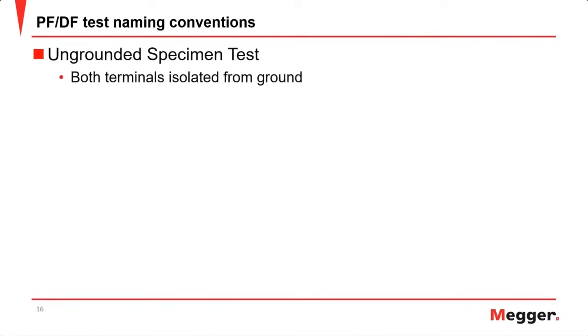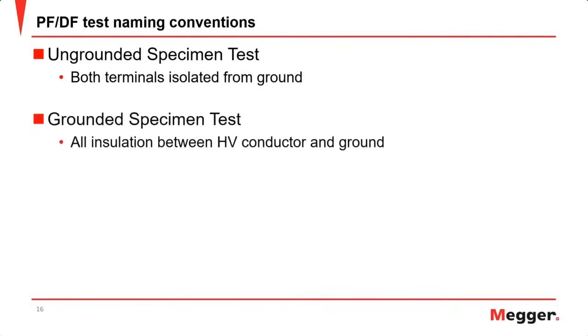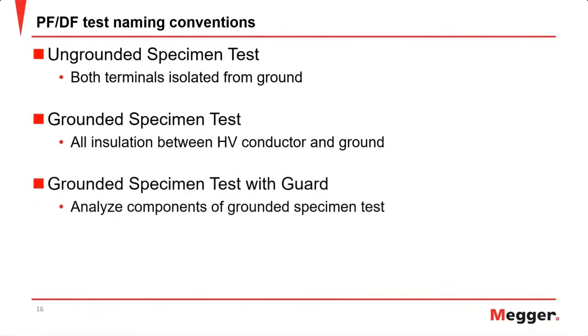And we do have a couple unique names when it comes to power factor testing. The first would be the ungrounded specimen test. This is where both terminals are isolated from ground. You then have a grounded specimen test, where all of the insulation between the high voltage conductor and ground is measured. And then you can do a grounded specimen test with guard. This is used to analyze the different components of the grounded specimen test. Since that grounded specimen test includes all of the current coming back on the red, the blue, and the ground, when you guard that out, you can use that as a confirmation of the other tests that you've performed.